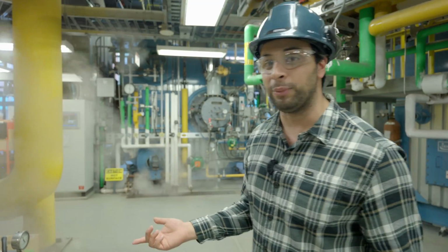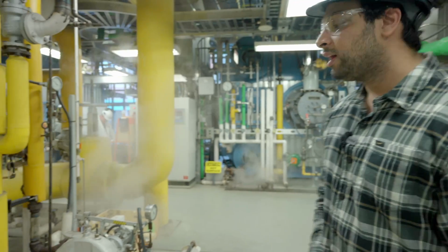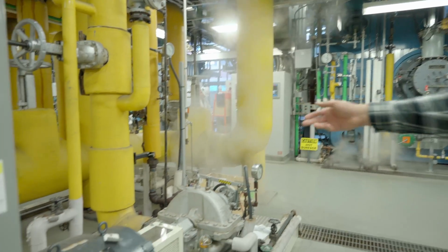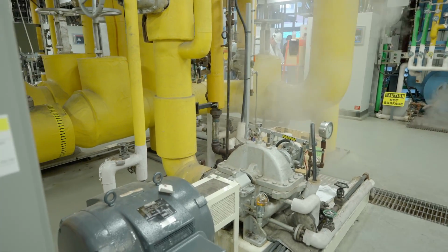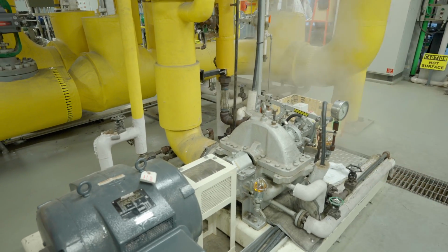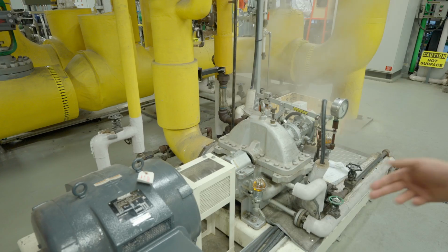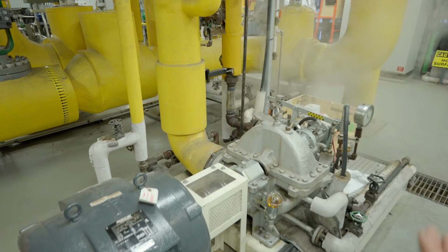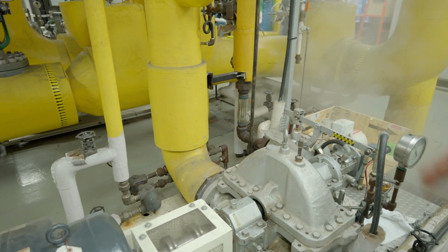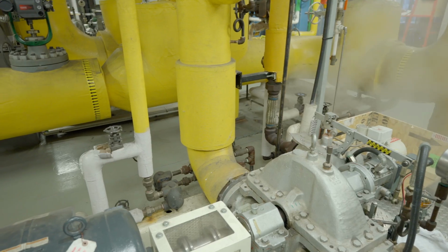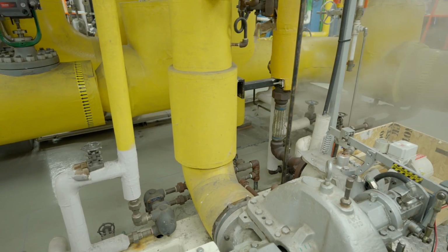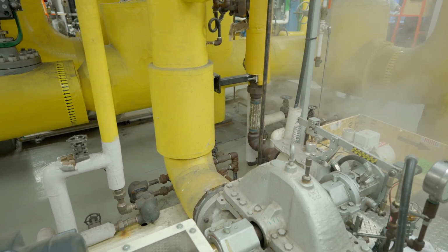And a similar principle applies when we're starting up the turbine here, that's why we have the bypass valve. As the components are heating up, we can just let all the condensate flow out into the drains while everything's getting nice and warm. And then once the shaft starts spinning and we've actually got movement, we can close those off, and the steam traps will do their job effectively, because we're not risking any cold pipes splashing everything back into condensate.